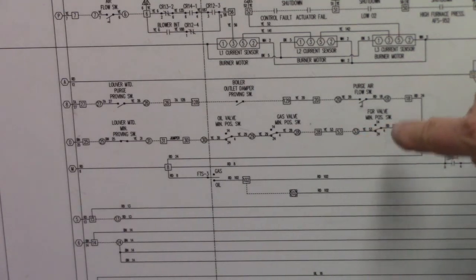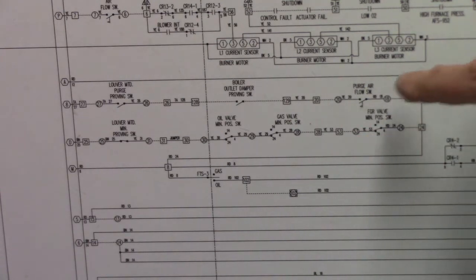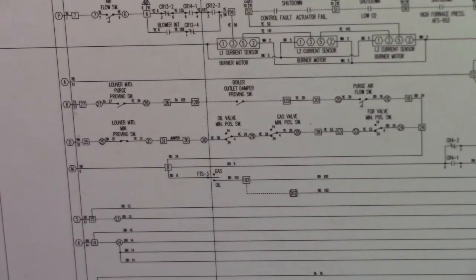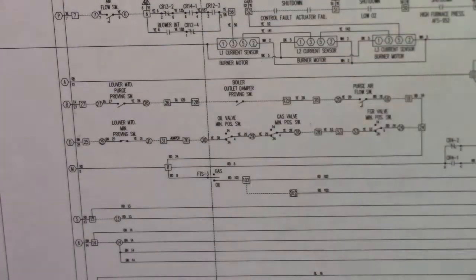So if we go out to the boiler, all we need to do is look at these three components to figure out why we're not going into purge. We don't have to worry about anything else on the boiler. It is one of these three components.